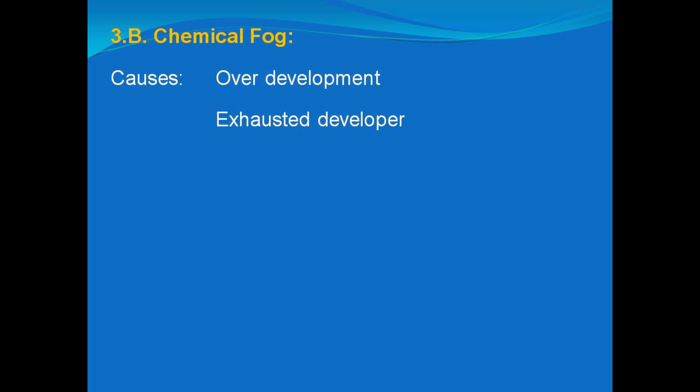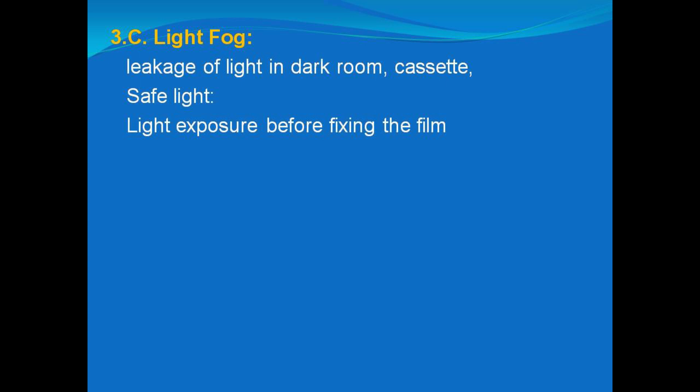Chemical fog can be due to over-development of the film, meaning we are keeping the film in developer solution for a long time, or our developer may be exhausted — meaning it is too old — so we shall replace the solution.